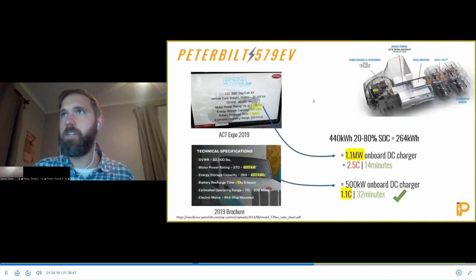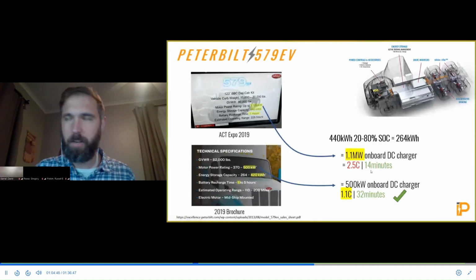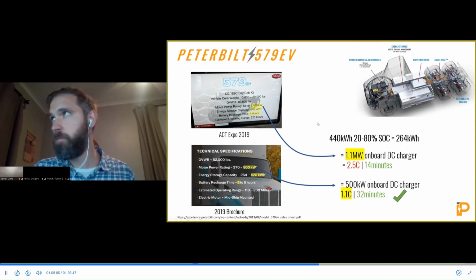To talk about some application examples, the Peterbilt 579EV — I took a photo of the specs from ACT Expo in Long Beach — said it has 1.1 megawatts worth of traction. I see it may now be revised down to 500 kilowatts. But if we take the 1.1 megawatts of traction and turn that into a charger with the switch, that would be able to charge at 2.5C. I always do my fast charging calculations between 20 to 80% SOC, so that would give 14 minutes as a fast charge, which doesn't fit with their 1 hour battery recharge time, which would be more like 1C. But at 500 kilowatts, we're more or less around 1C, so that's a 30-minute fast charge, 20 to 80% SOC. That seems pretty good.